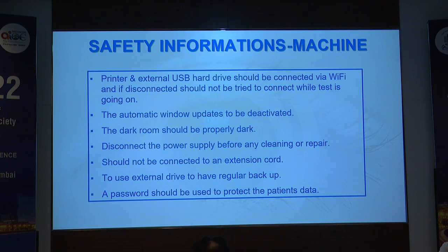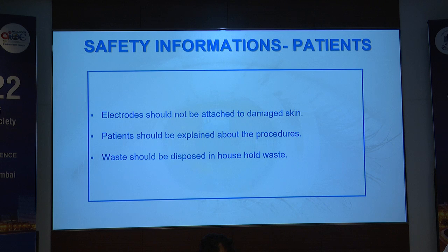Safety information regarding the machine: remember, if you are using a printer or external USB hard drive, it should be connected via Wi-Fi. Automatic Windows updates should be deactivated. The dark room should be properly dark. Disconnect the power supply before any cleaning. It should not be connected to an extension cord. Use an external drive for regular backup, and a password should be used to protect the patient data. Electrodes should not be attached to damaged skin. The patient should be explained the procedure, and waste disposal should be done thoroughly in household waste.